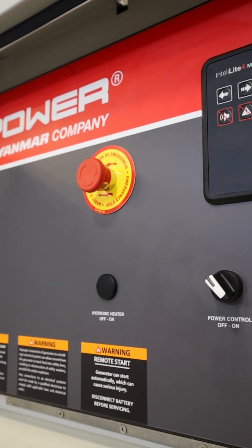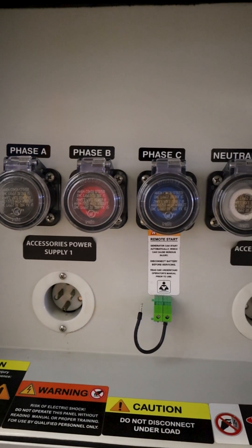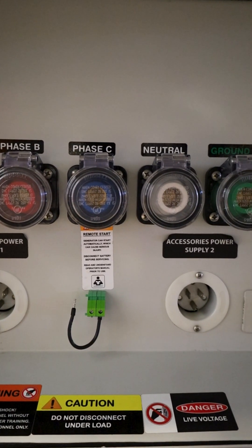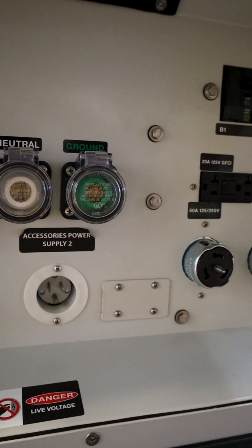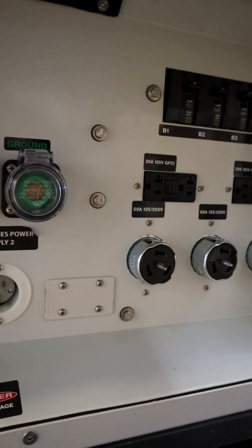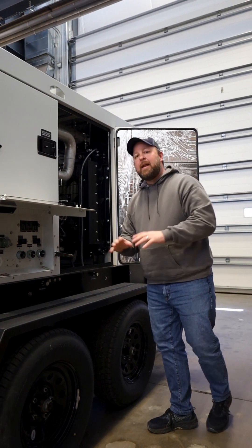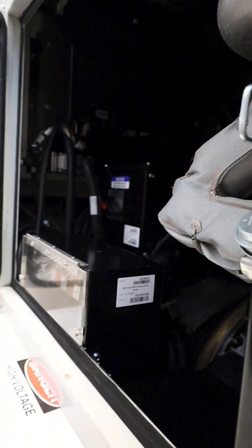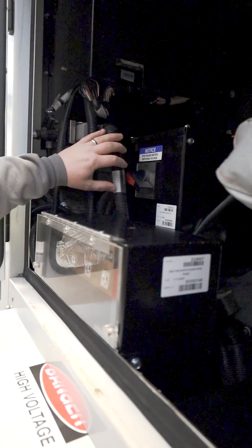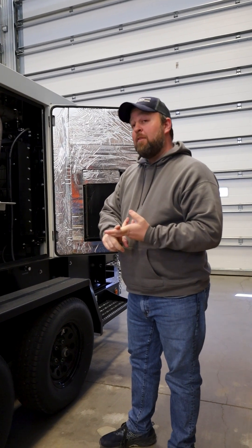Speaking of versatility, this unit is pretty exciting because we have all of our Camlock connections here. We also have 50 amp breaker single phase 240 connections and 20 amp breaker single phase 120 volt connections down here. This makes the unit usable in any situation, because on top of that, up here we have a multi voltage selector switch. They can go back and forth between single phase 120/240, 120/208 three phase, and 277/480 three phase.